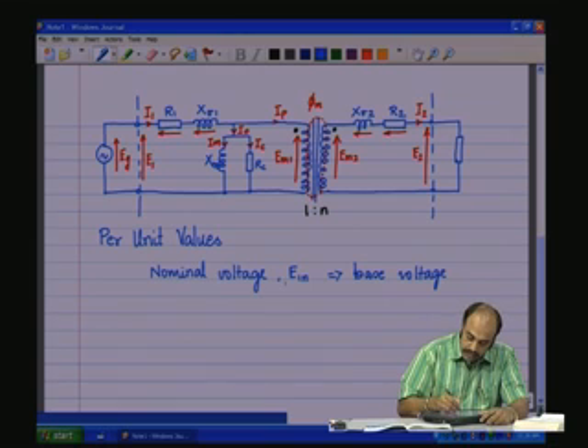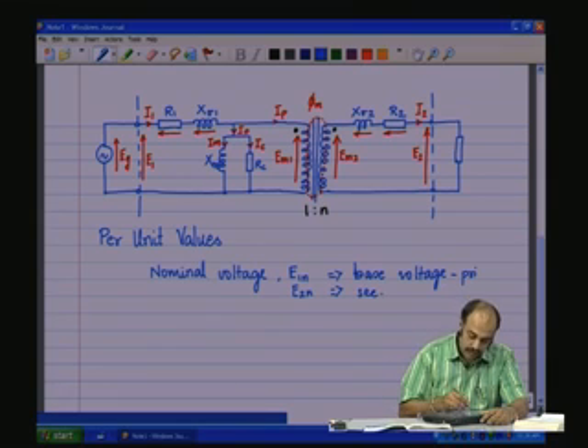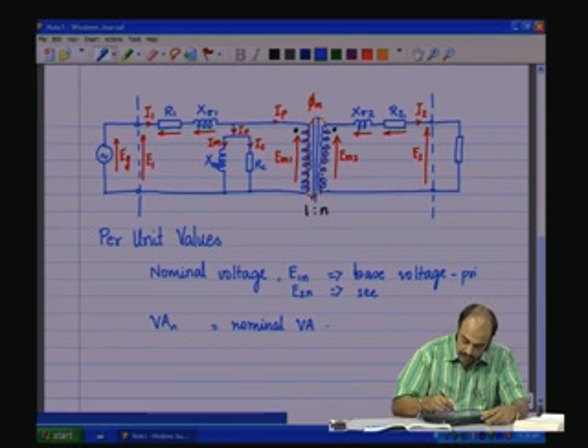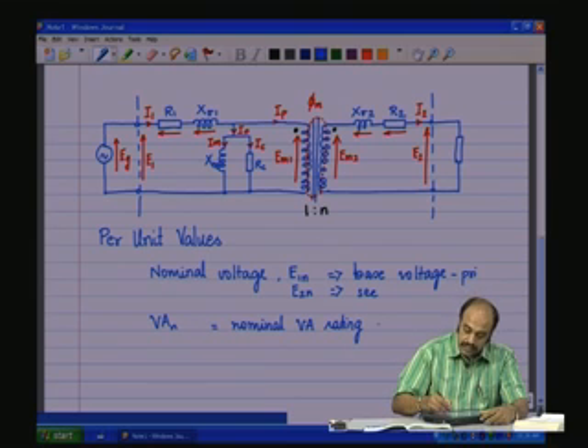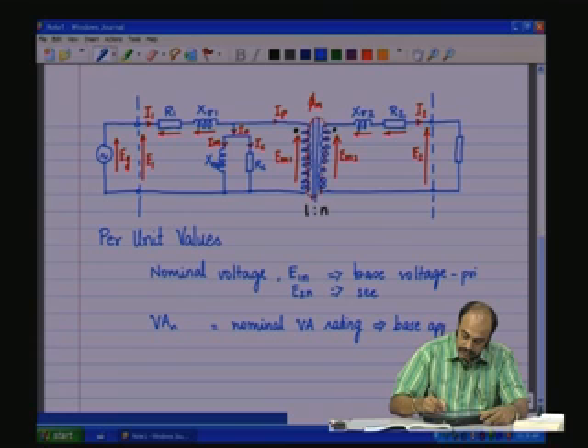For the primary, and E2 nominal, that is whatever is the rated voltage, as the base voltage for the secondary. This is for the primary and this is for the secondary. The VA rating nominal, VAN, which is the nominal VA rating, the apparent power rating of the transformer, is considered as the base apparent power.